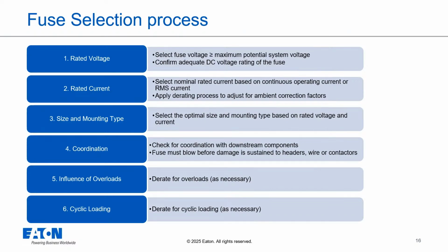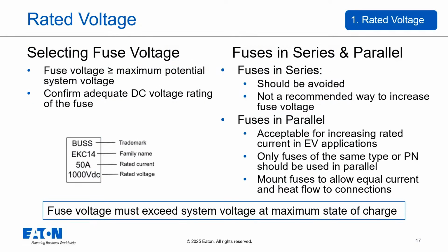Let's circle back to selecting the rated voltage. As mentioned, the fuse voltage must be greater than or equal to the maximum potential system voltage. It's also vital to confirm that the fuse has an adequate DC voltage rating, as DC interruption is more challenging than AC. Speaking of voltage, fuses in series should generally be avoided. It's not a recommended way to increase the effective fuse voltage rating.